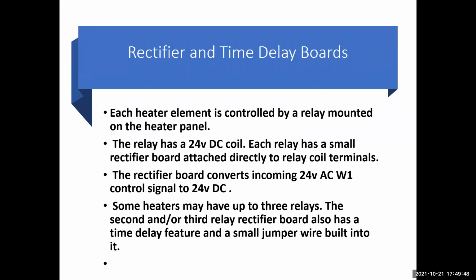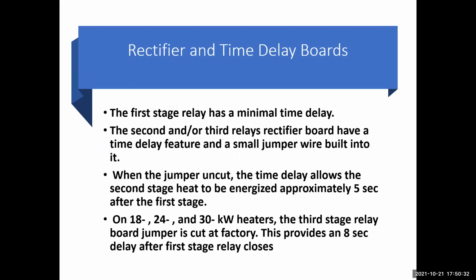Each heating element is controlled by a relay mounted on the heater panel. The relay has 24 volts DC. Each relay has a small rectifier attached directly to the relay coil terminals. The rectifier board converts the incoming 24 volts AC W1 controlled signal to 24 volts DC. Some of the heaters may have up to 3 relays. The second and third relay rectifiers also have time delay features and a small jumper built into them. The first stage relay has a minimum time delay. We're talking 1 to 2 seconds.